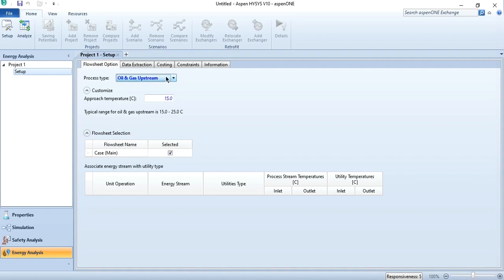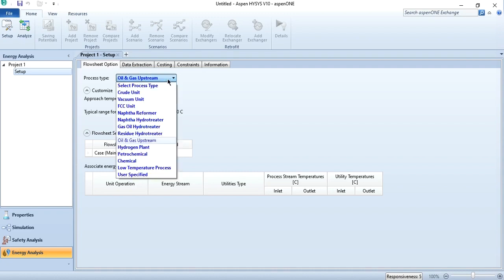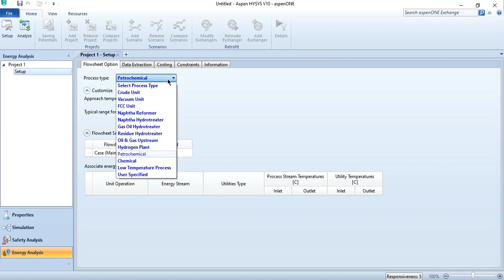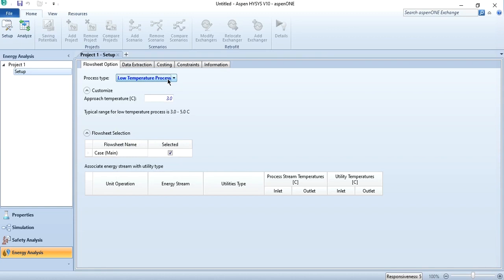For oil and gas upstream processes, the value is between 15 to 25 degrees centigrade. For hydrogen plants where hydrogen is produced, the range is 20 to 30 degrees centigrade. For petrochemical, the range is 10 to 20 degrees centigrade. For chemical systems, again 10 to 20 degrees centigrade. And for low temperature processes, where the system is operated below ambient — like an air separation unit, which is a cryogenic separation process — this range can go to 3 to 5 degrees centigrade.